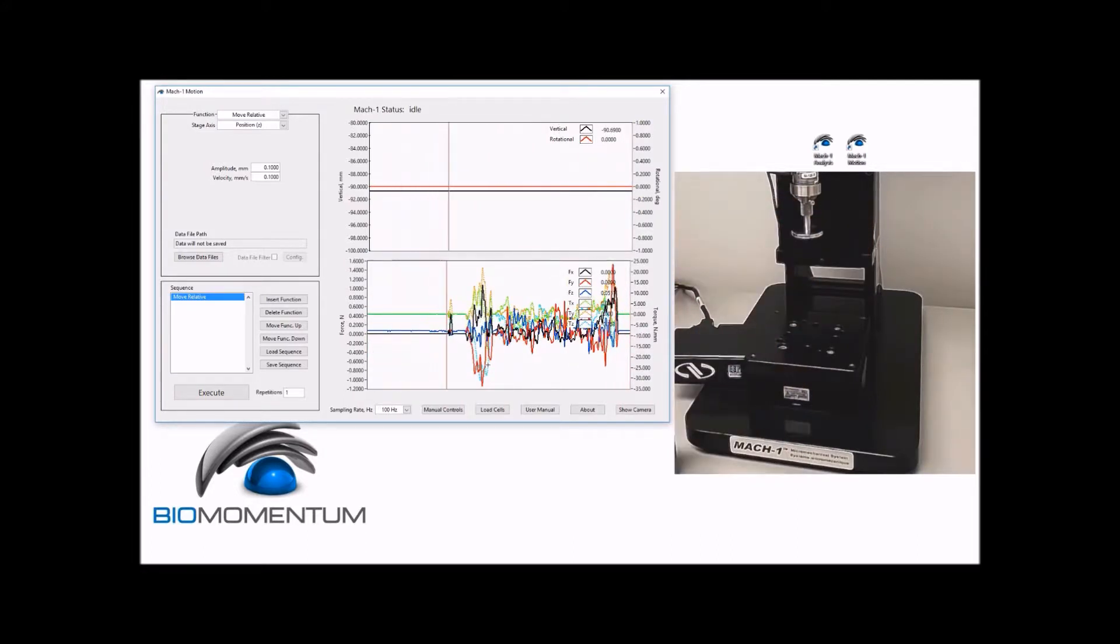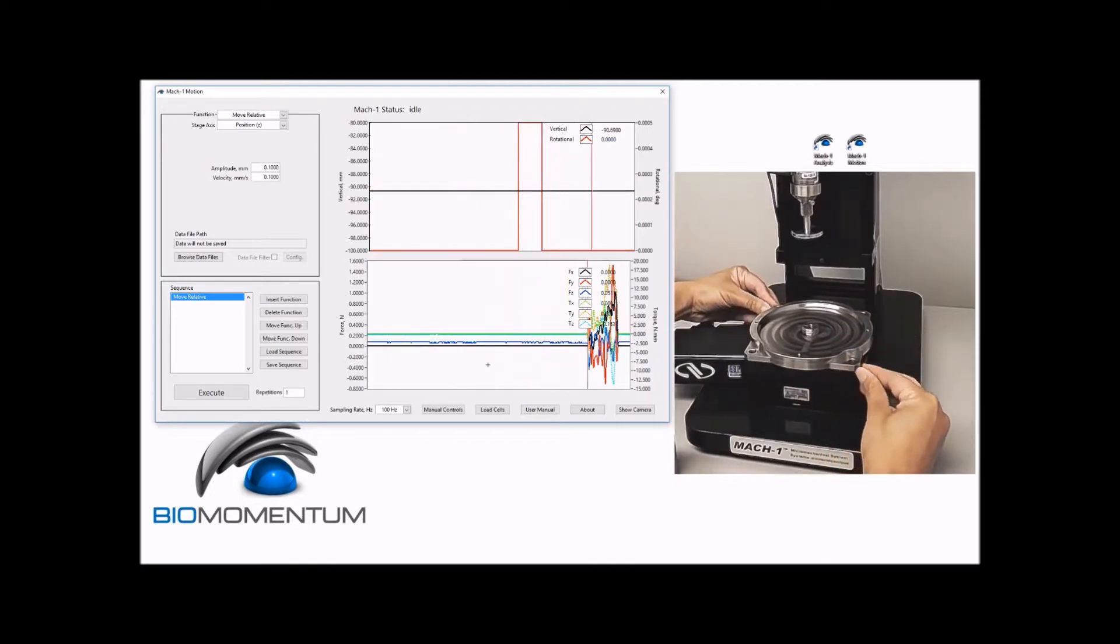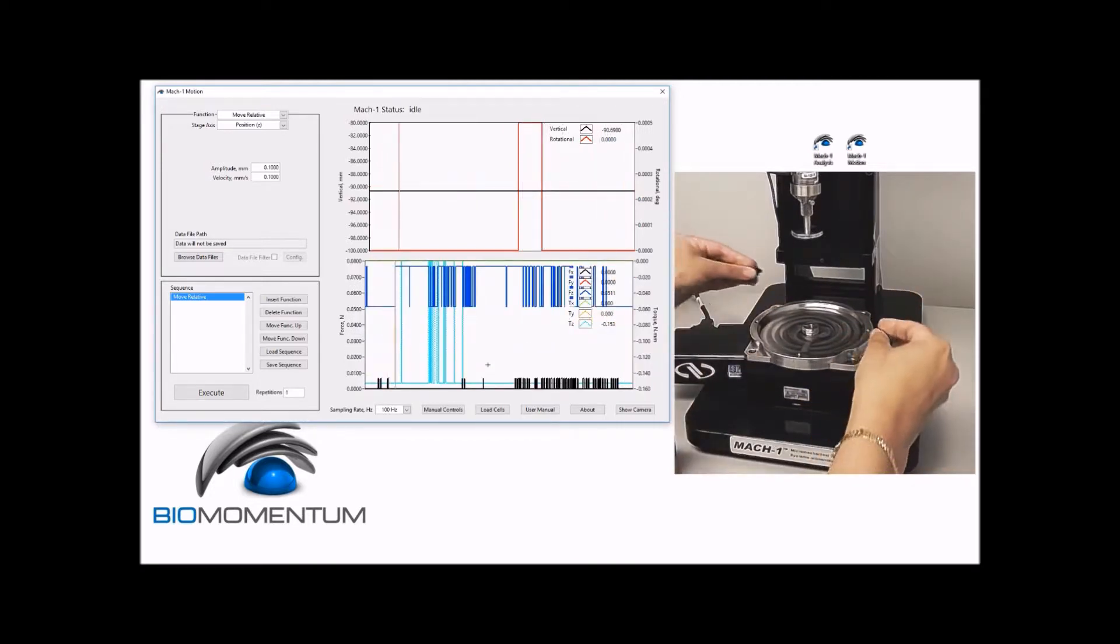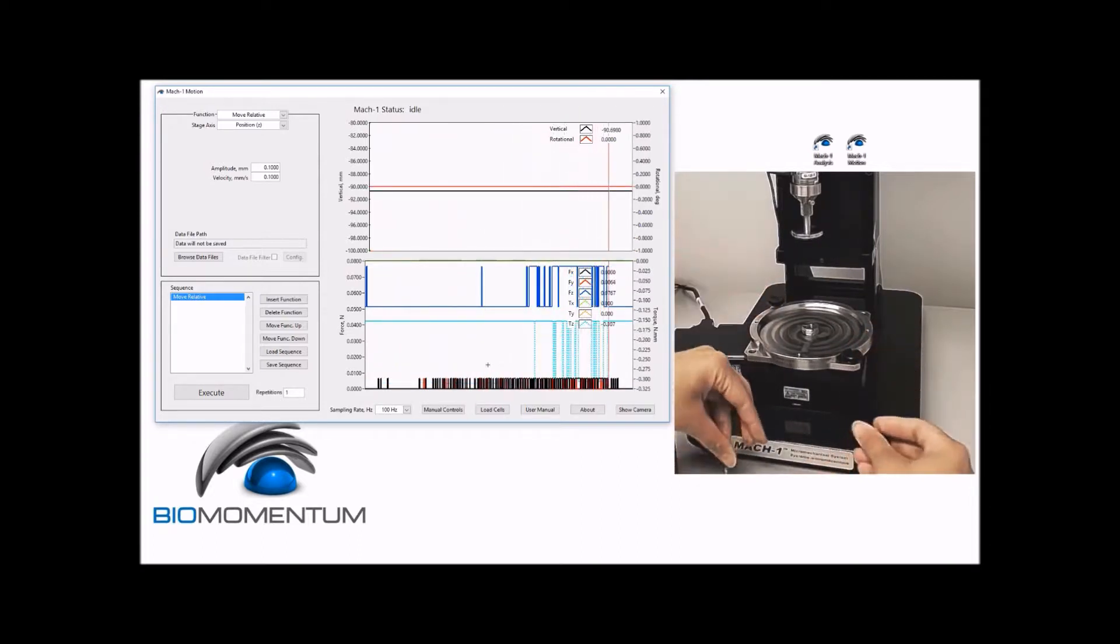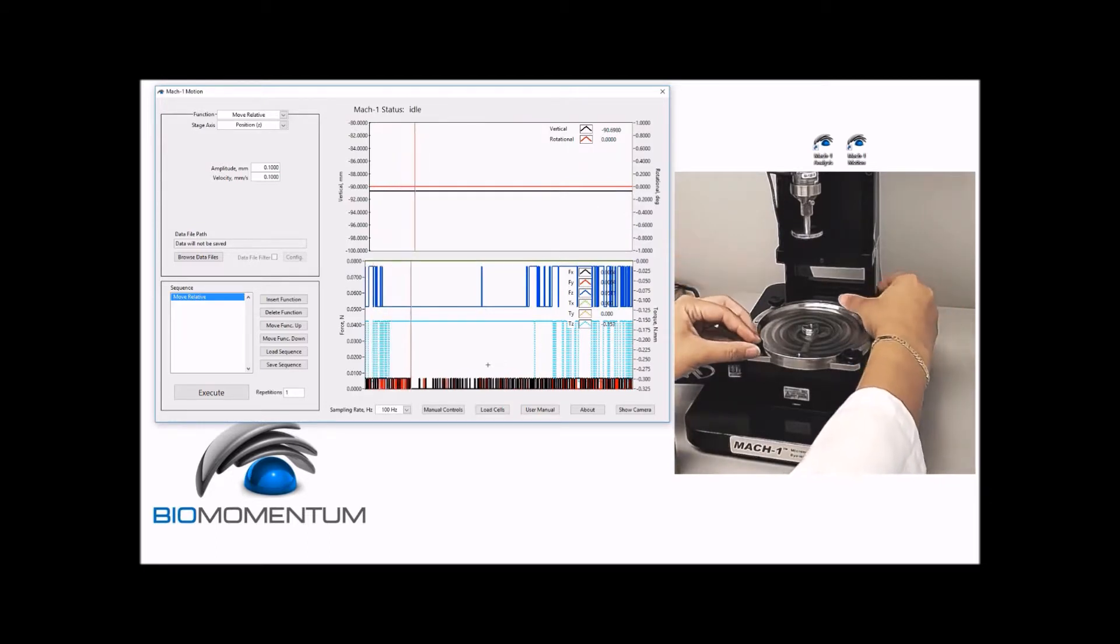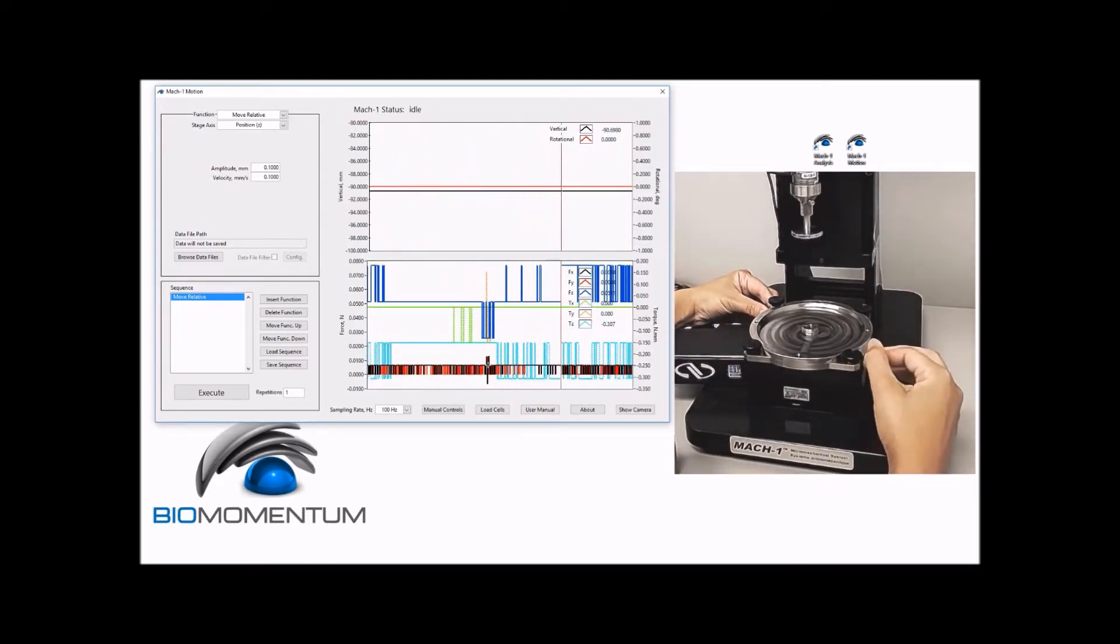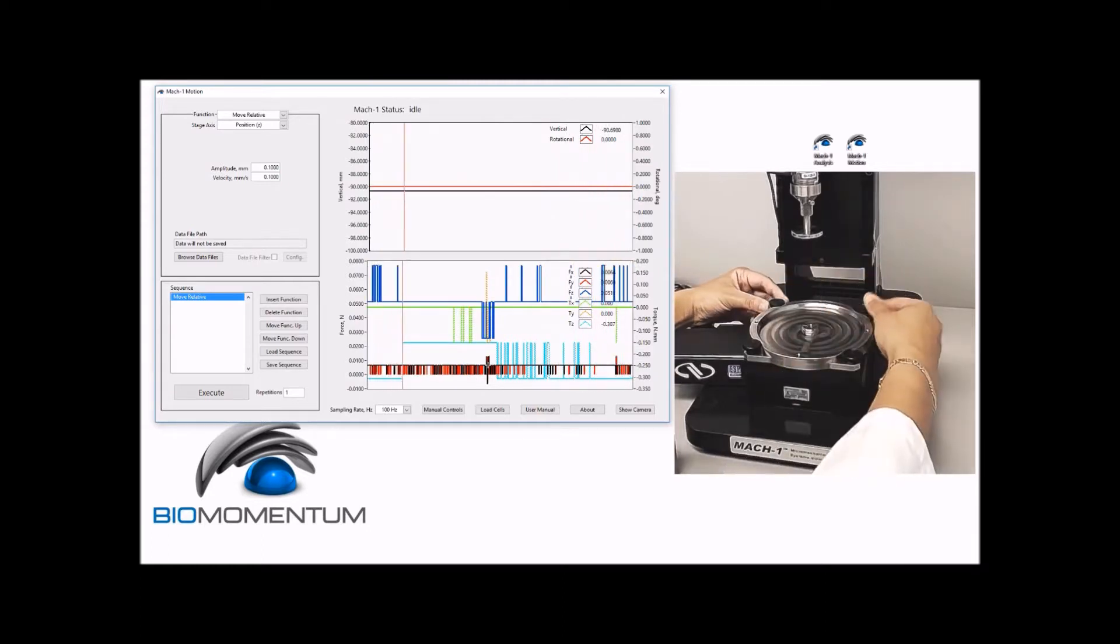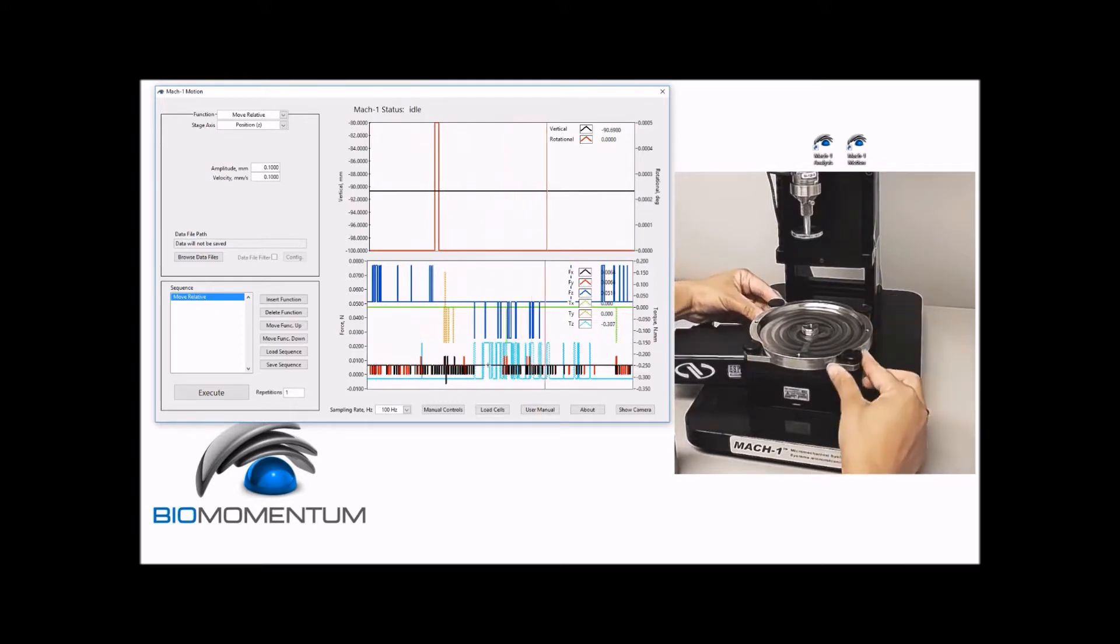Then secure the testing chamber onto the rotational stage using the four screws. It is essential that the rotational stage central axis be aligned with the center of the multi-axial load cell. Perform any necessary adjustments in the stage axial alignment using the four screws to ensure that the testing chamber is perfectly aligned on the rotational stage.